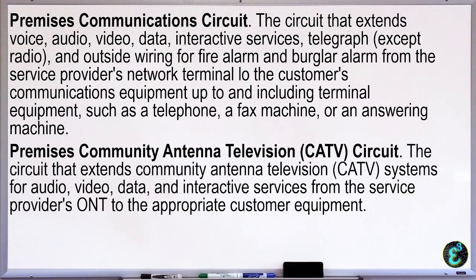All, this is all communication circuits. So ito na sinabi ko, the clearance and the spacing, the standards that apply to communication circuits will apply also to every type of communication circuit that you are going to install in a building. So yung mga 300 mm, 2.5 from the roof, so the vertical clearance, all of that will apply as long as the wire or the conductor is part of the communication circuit, either that is broadband, fiber, telephone, cable TV, CCTV, fire alarm. So as long as it carries signals, no, nakikiraan ang signal either for emergency or for entertainment, so it will follow the standard for communication circuits, no?